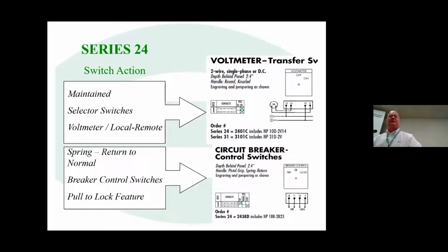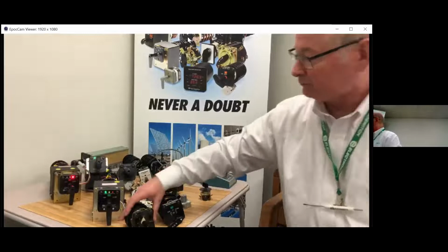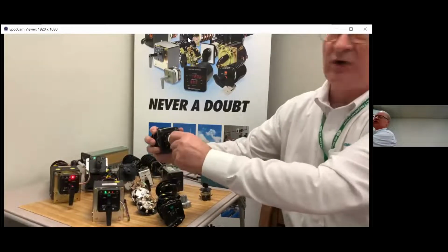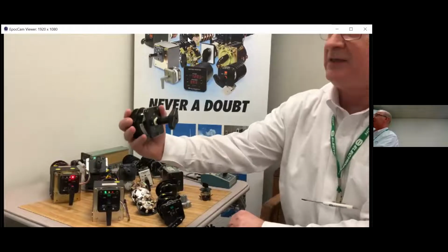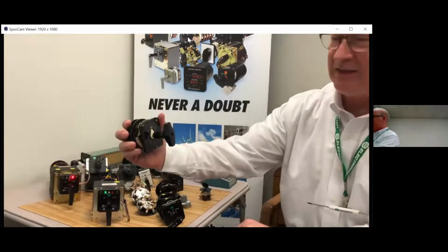If I now go to my types of switches, we talked a little bit about the Series 24 and some applications. 2 of the basic applications for a switch is to have a maintain selector for like a local remote switch or a voltmeter switch, or a spring return style switch for breaker control. And let me show you those real quickly here. So we did talk about a maintain switch. So when I move it in that position, it maintains in that position. When I come back, it comes back and is maintained in that position.